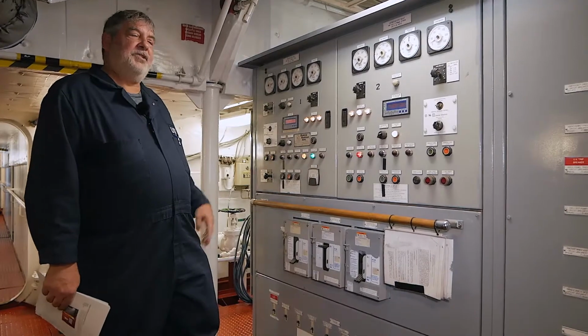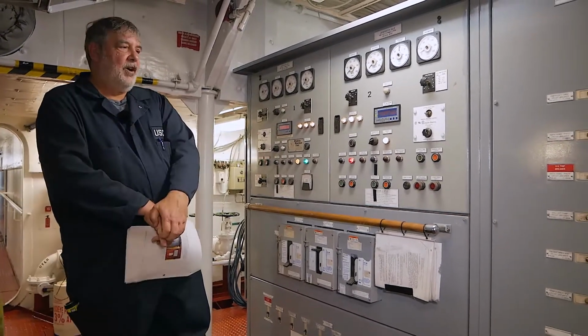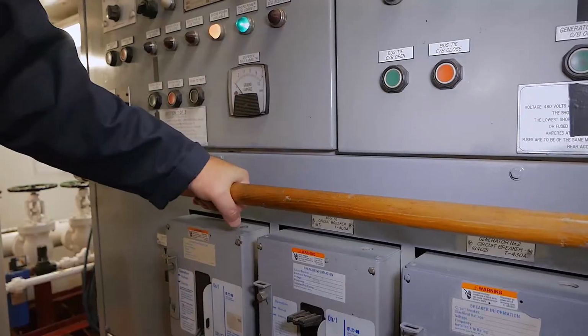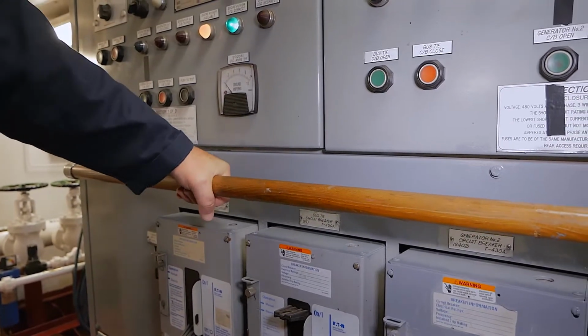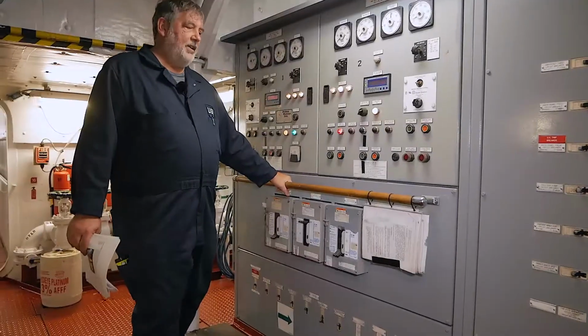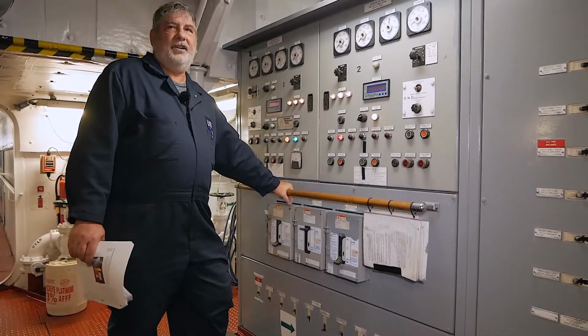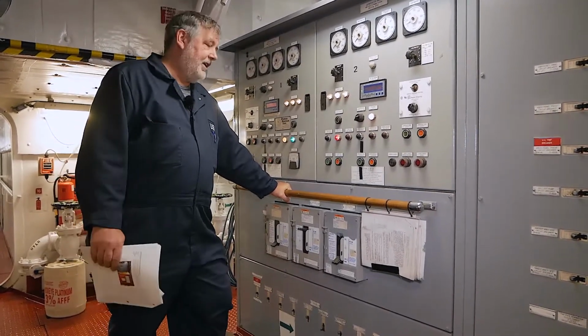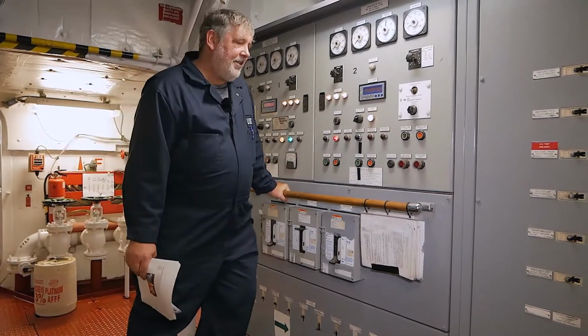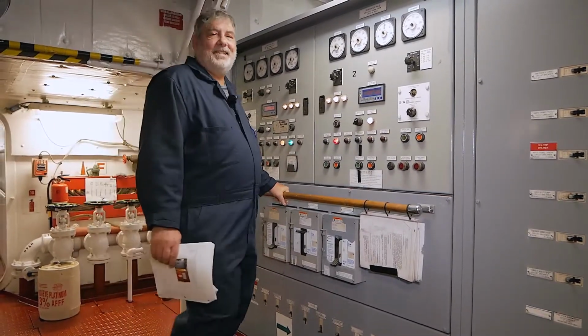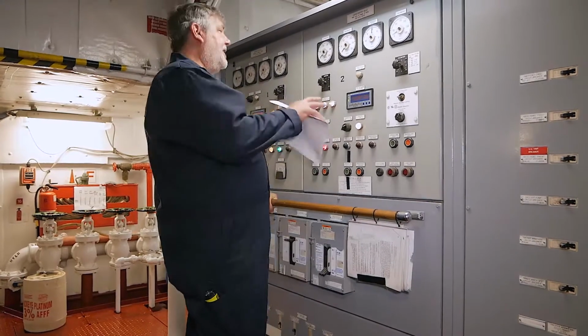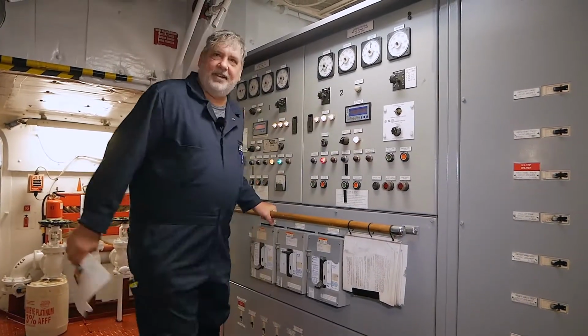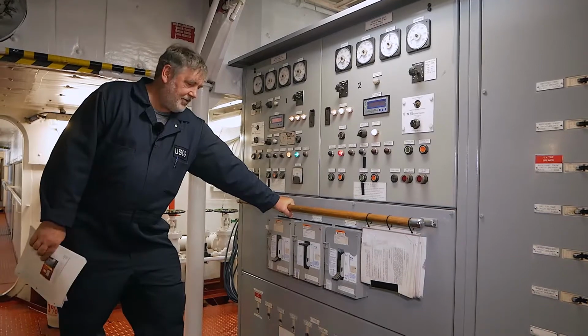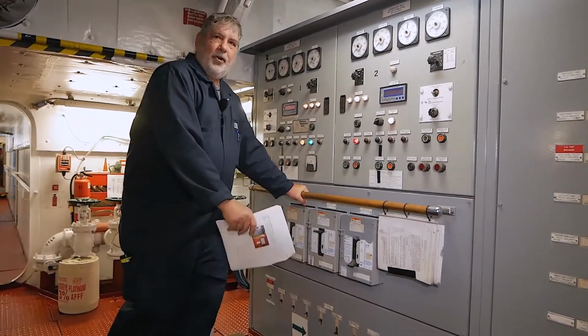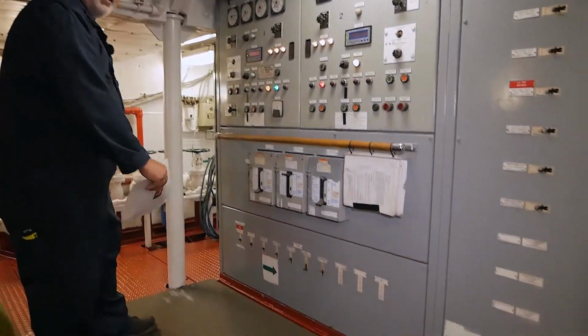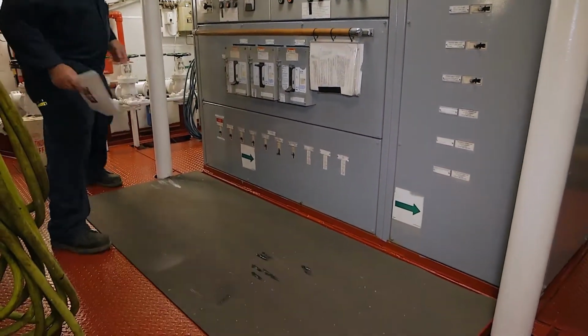Okay, the safety features of a switchboard are going to be the non-conductive handrail. In this case, it's made of wood. It could also be made of other non-conductive materials such as bakelite. The purpose of this handrail is so that when you're in seas, you have something to help steady you so you don't accidentally fall into and damage the controls. Switchboards also require electrical safety matting in front of them.